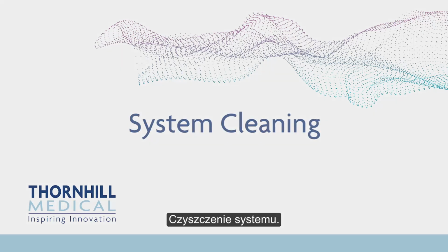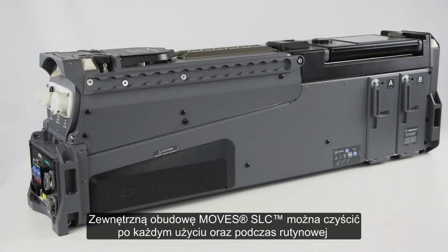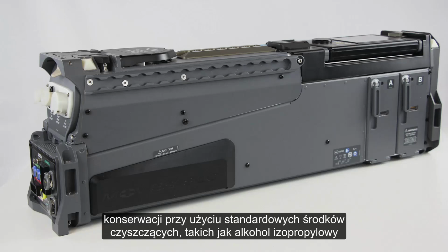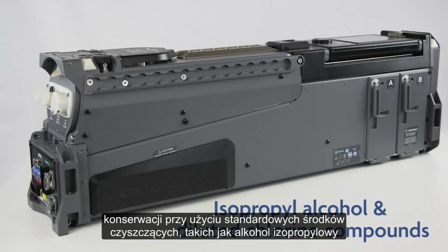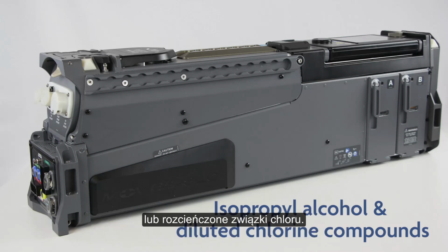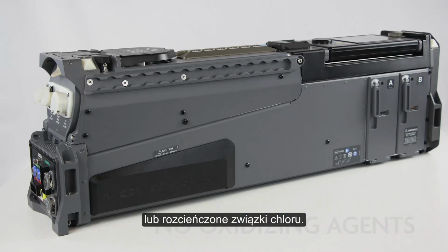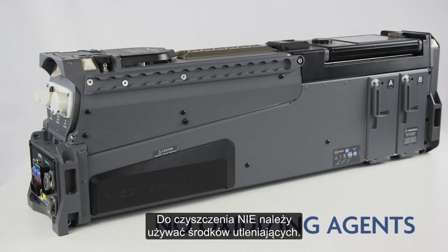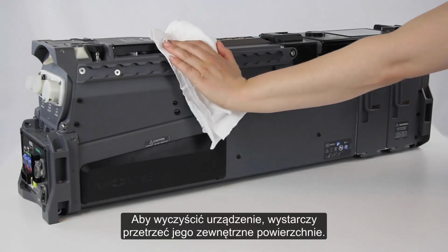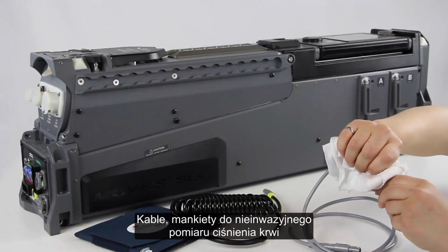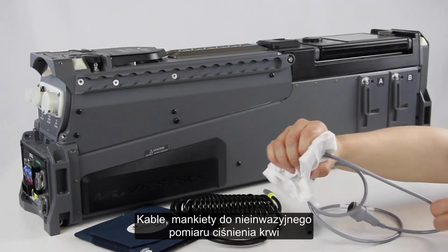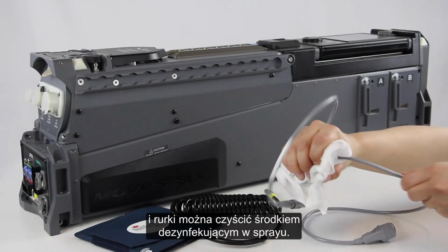System cleaning. The external body of Moves SLC can be cleaned after each use and during routine maintenance using standard cleaning agents such as isopropyl alcohol or diluted chlorine compounds. Oxidizing agents should not be used for cleaning. To clean the device, simply wipe down the external surfaces. Cables, non-invasive blood pressure cuffs, and tubing can be cleaned with disinfecting spray.